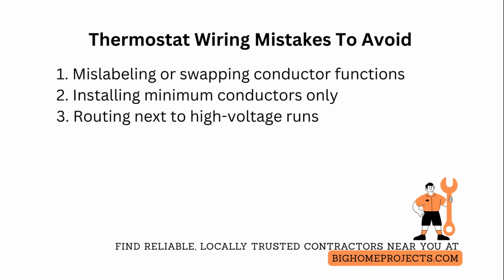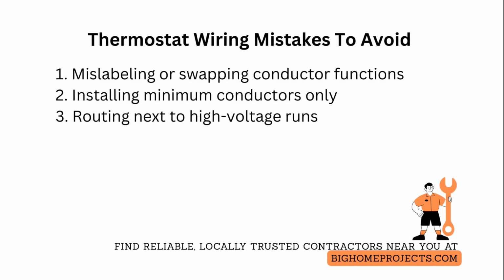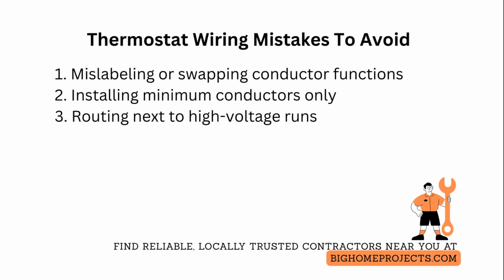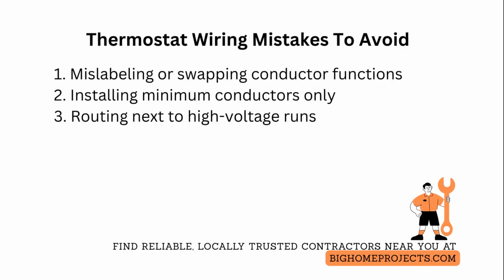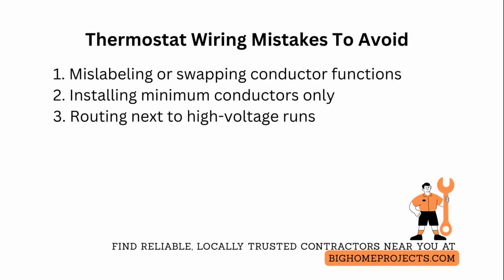The clear fix is to install a 6-wire cable, even when 5 are required, so you have a dedicated spare conductor. One of the frequent problems technicians face is routing thermostat wiring next to high voltage runs, causing signal interference or tripped breakers. Correct this by maintaining separation, using shielded cable if necessary, and keeping transformer grounds and common wires properly bonded.